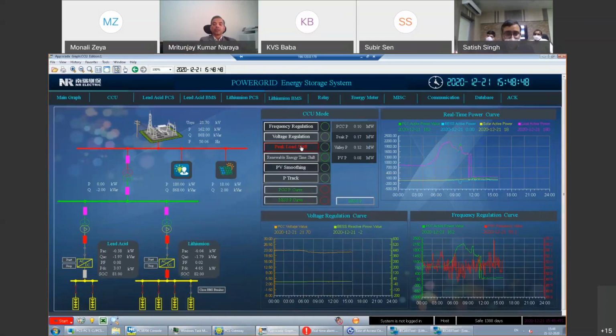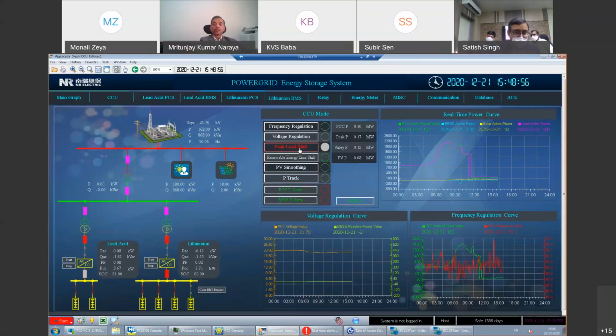Peak load shift, yeah. So again, in the peak load shifting, here we see there is a load connected that is 180 kilowatt, right? And then our objective here is to provide a band of the loading conditions, so maximum peak and valley peak. So for example, let's set these values at 170 kilowatt and 120 kilowatt.